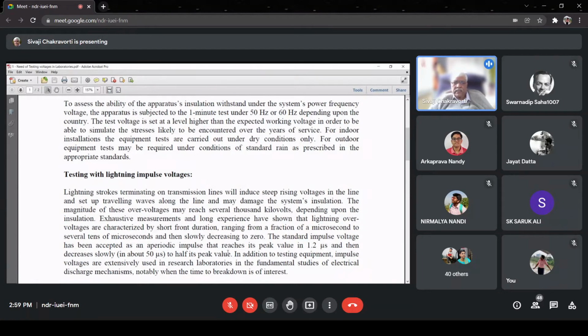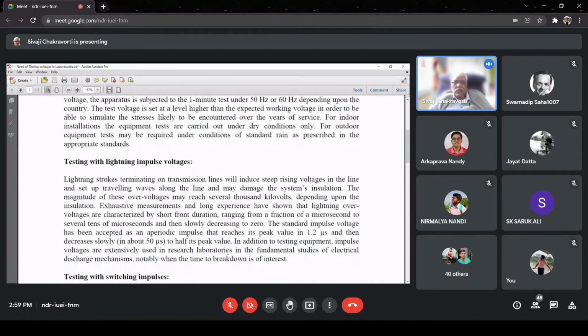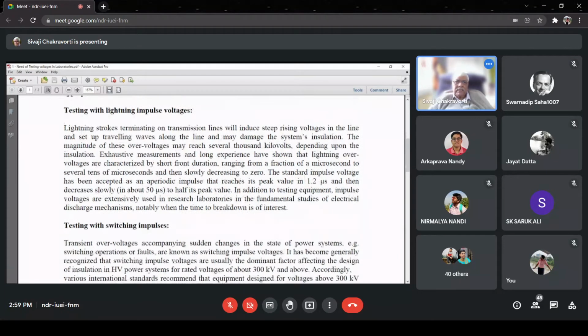Because if you don't do that, then whatever results you get is not as per the real life situation. But then, apart from the natural lightning which generates such impulse voltages, there is a second source also. What is that? That is called the switching of the electrical components. Whenever we do some switching, and switching in a large power system is very, very common. We switch on and off the load, several equipment, capacitors, this and that. So switching is very common.